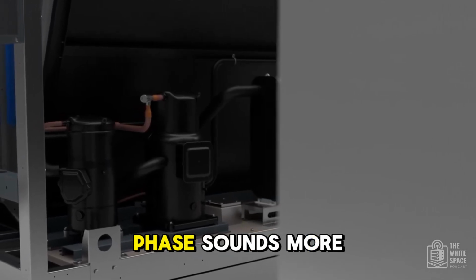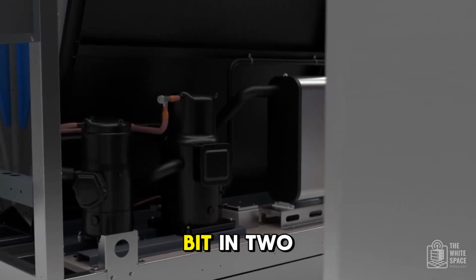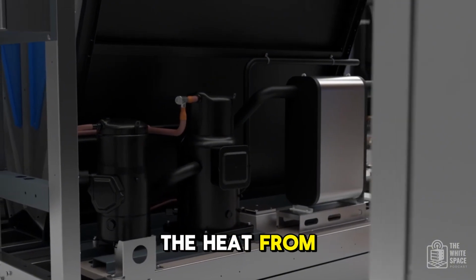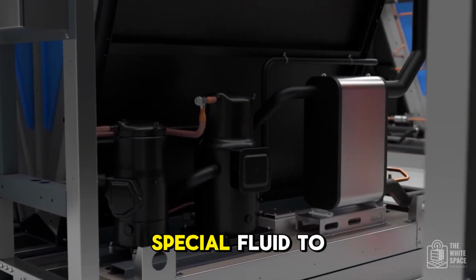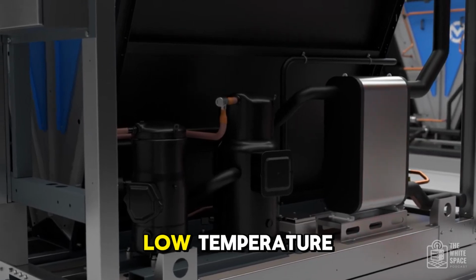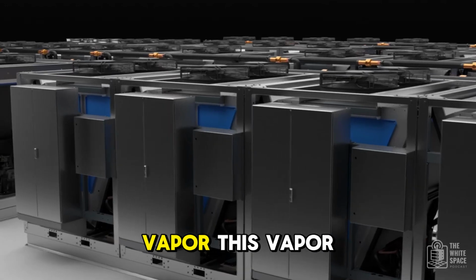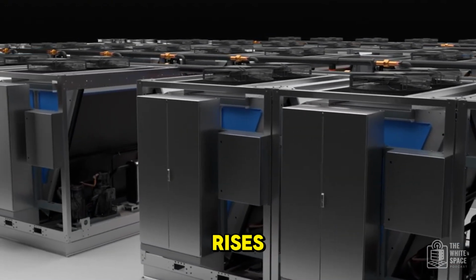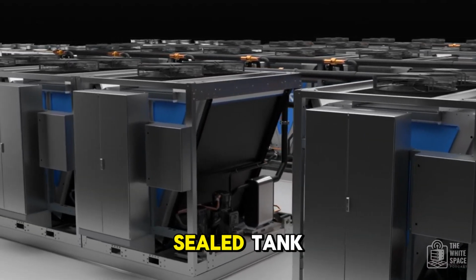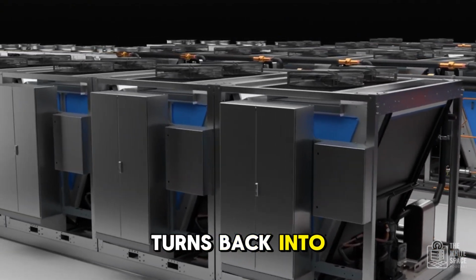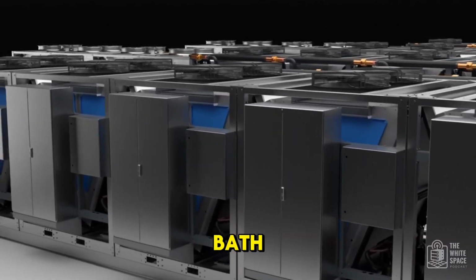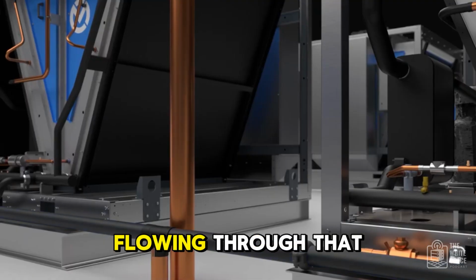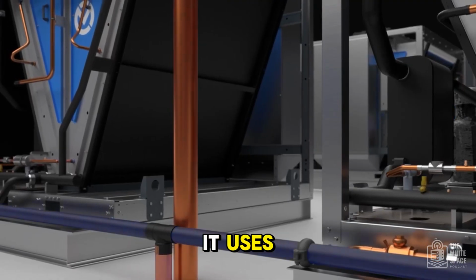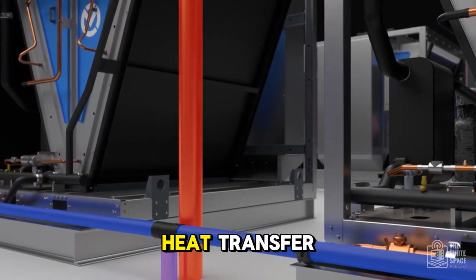And two-phase sounds more complex. It is a bit. In two-phase immersion, the heat from the chips actually causes the special fluid to boil at a relatively low temperature. It turns into vapor, which rises, hits a condenser coil at the top of the sealed tank, cools down, turns back into liquid, and drips back into the bath. The heat is carried away by the coolant flowing through that condenser coil. It uses the phase change for really efficient heat transfer.